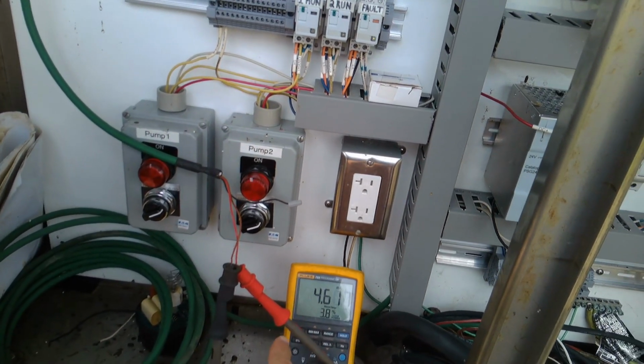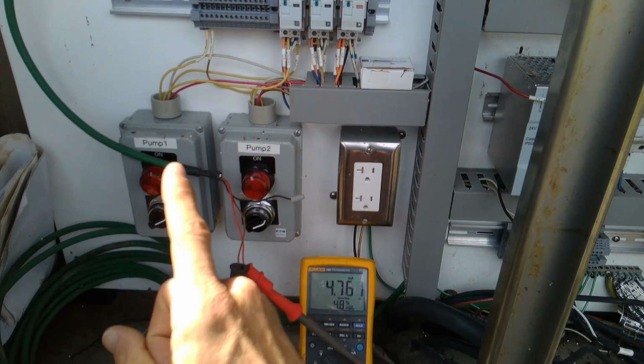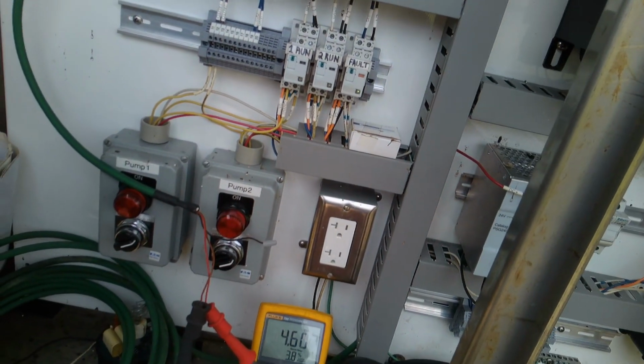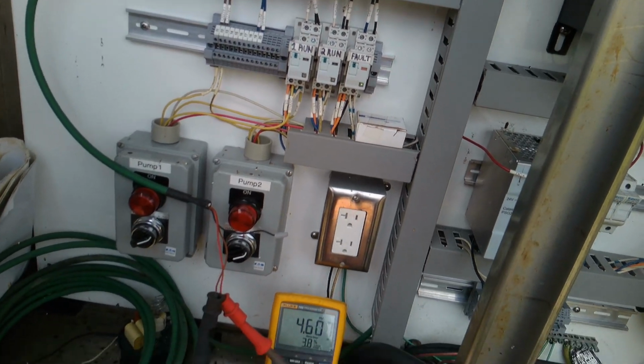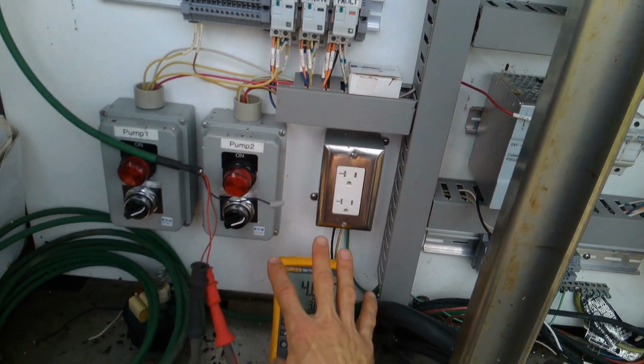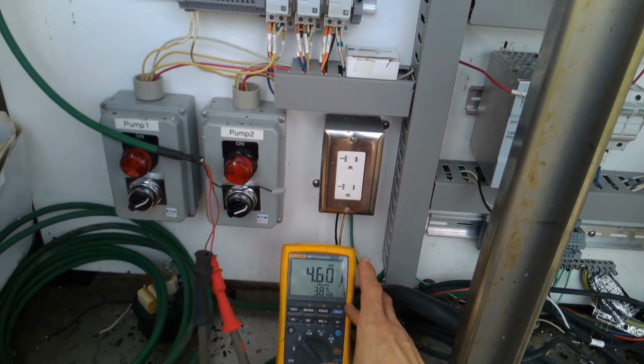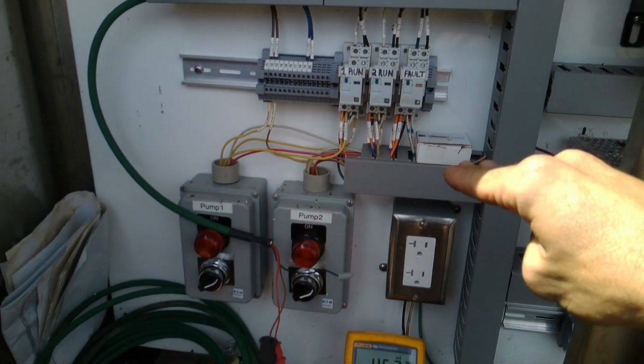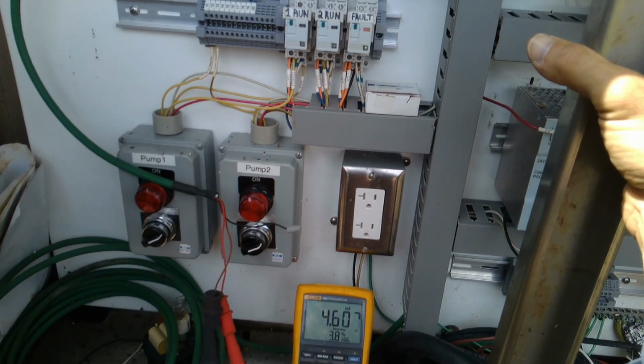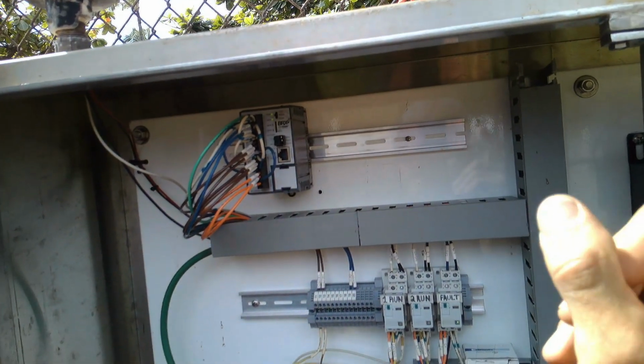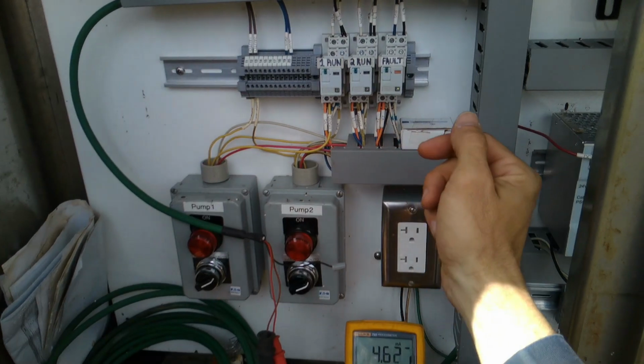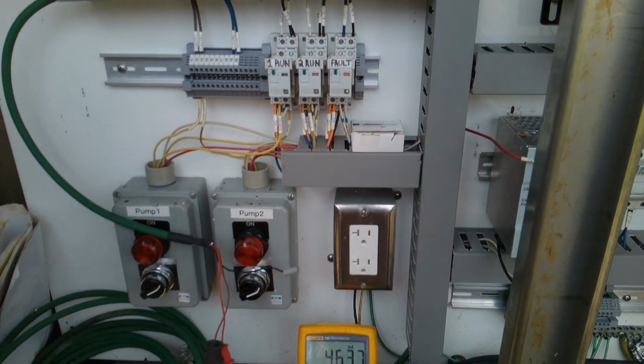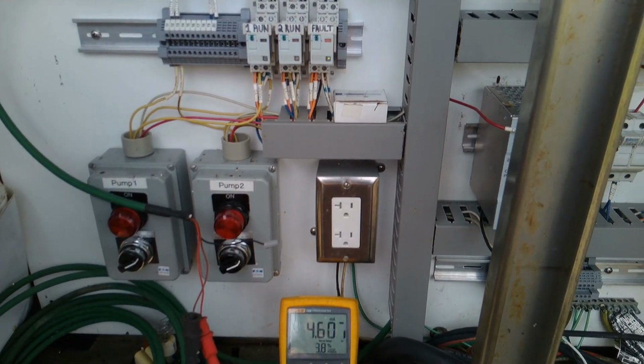Well, the next step I'd say we'll put this into the PLC, and then we'll look at the raw value on the PLC, and then I can use this guy and have him pretend to be a transducer and generate a 4 to 20 milliamp signal. If I put a clean, solid signal into my PLC and the signal stays clean and solid, then I'm happy with the input, and I'll probably recommend they get the transducer replaced. But I want to verify that the input to the PLC is good before I just say change the transducer and get the hell out of here, because it could be more than one problem at once. It's usually how it goes.